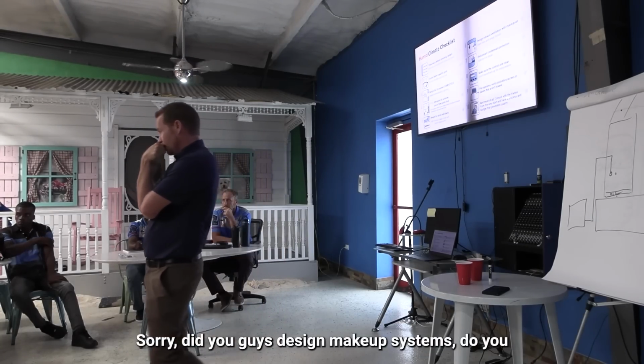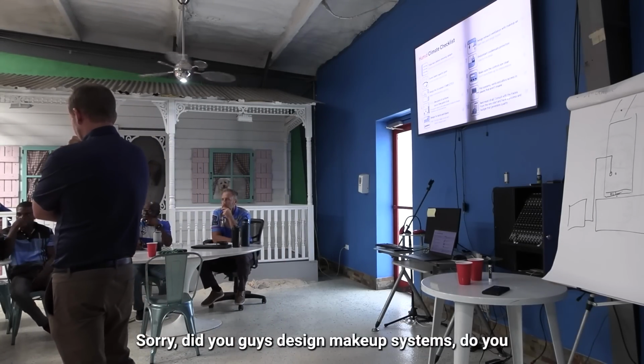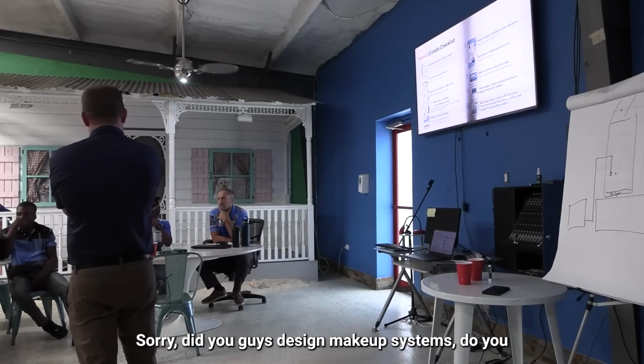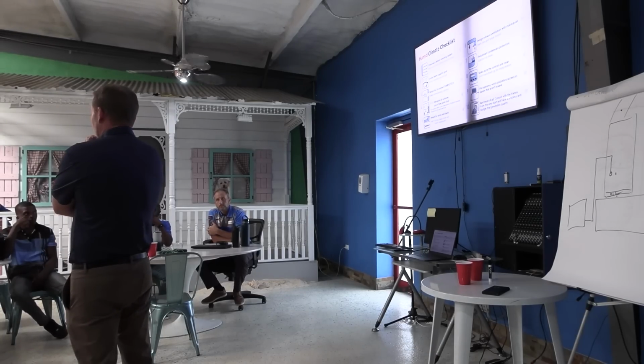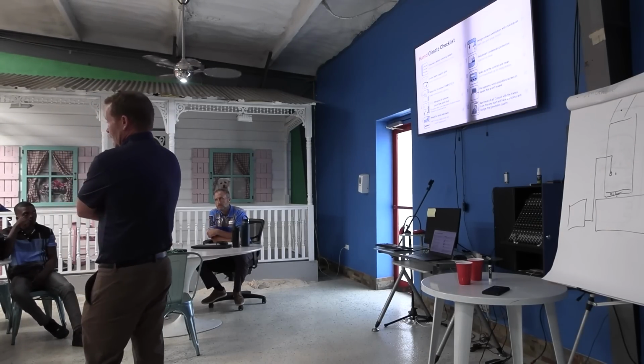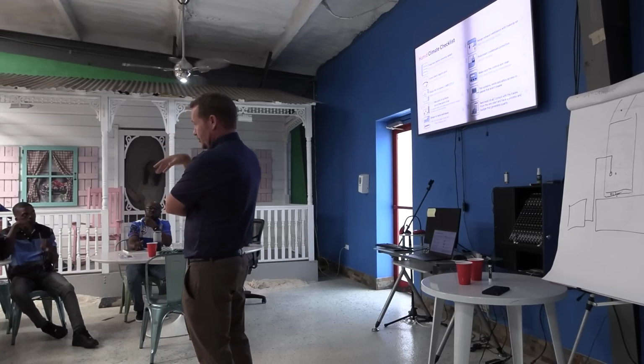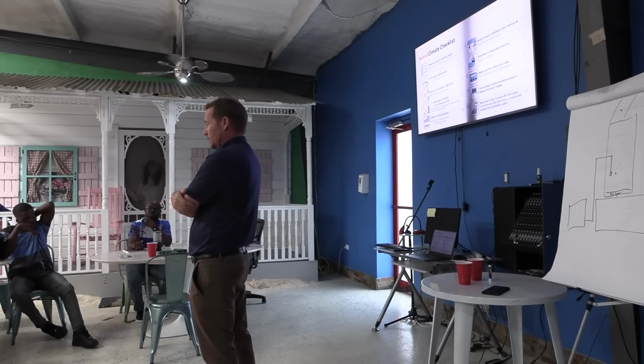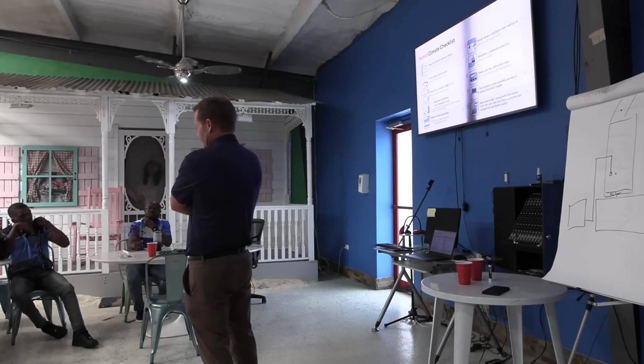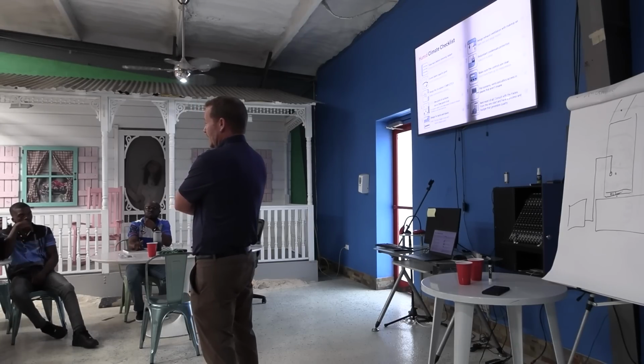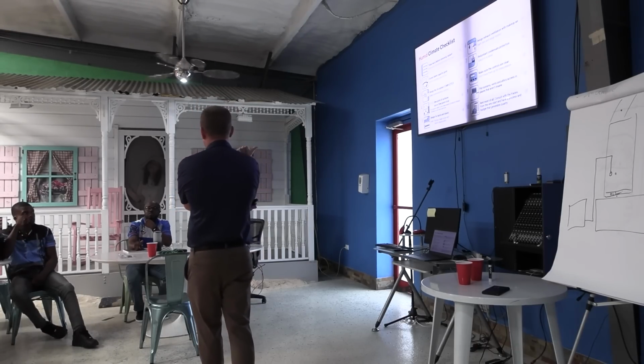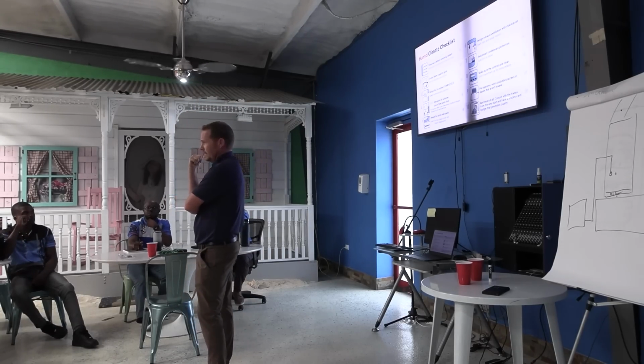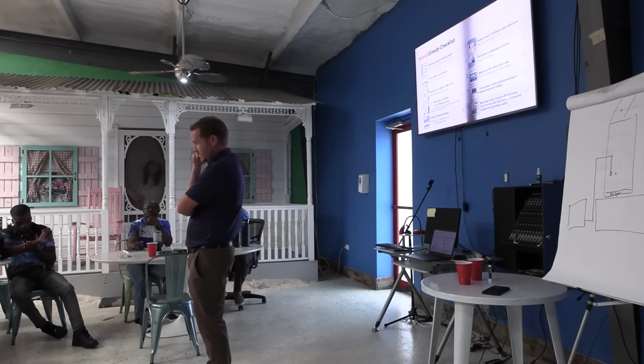Sorry, going back to number 6, let me interrupt. Did you guys design makeup air systems? We work with a company that actually does designs anytime you have these more complicated, bigger systems. We mostly only do this in commercial, but in Florida, anytime you have an exhaust that's more than 400 CFM, by code you have to have a makeup air system as part of it.